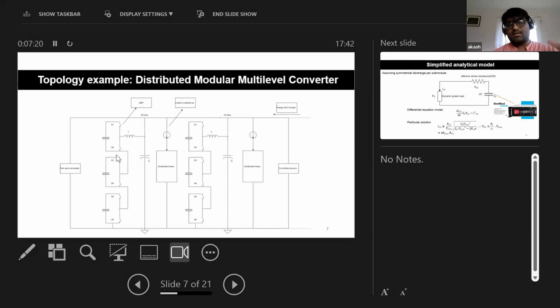In the previous example, cascading circumvents it because the voltages are in parallel, so there's no stacking on the ultracapacitor side. In the MMC case, they are technically stacked, but they're not all on at the same time, so you only get high voltages instantaneously rather than it being a consistent thing. That's how you circumvent that hard limit of 1,500 volts in series.